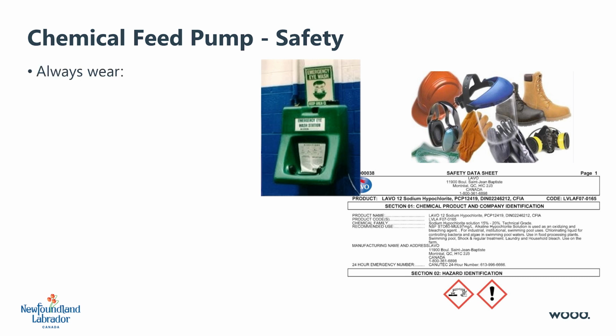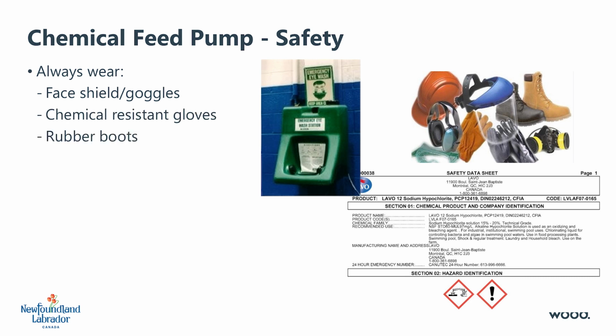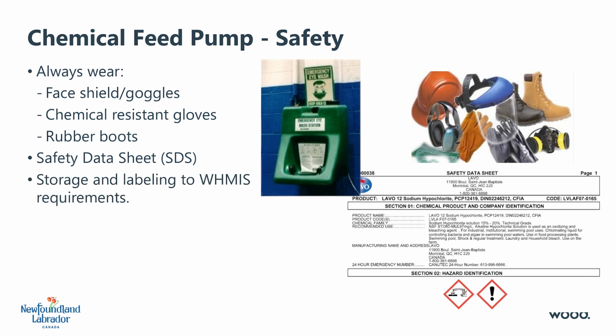Operators should always wear a face shield or safety goggles, chemical-resistant gloves, and rubber boots when working around chemicals. The applicable safety data sheets, or SDSs, for all chemicals used should be available and stored in a location where they are easily accessible. Ensure all chemical containers are labeled and stored as required by WHMIS guidelines, and at any location that chemicals are being used, there should be an emergency eye wash and shower station installed and operational. Prior to using any chemical, operators should obtain and review the applicable SDS.